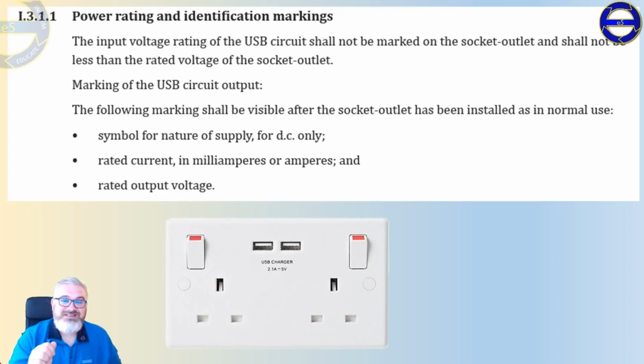The more interesting part is it states marking of the USB circuit output. The following markings shall be visible after the socket outlet has been installed as in normal use. So that's when the electrician has finished, put his screw caps on, issued a minor works or an electrical installation certificate, which he should be doing, and it states very clearly that the markings visible should include the symbol for nature of supply, for DC only, which is that bit there, the rated current in milliamperes or amperes, 2.1 or 2100 milliamps, and the rated output voltage.